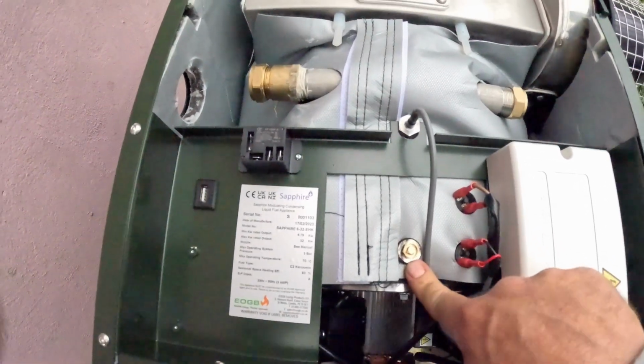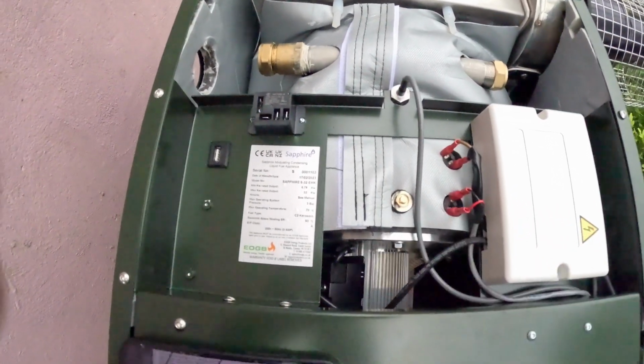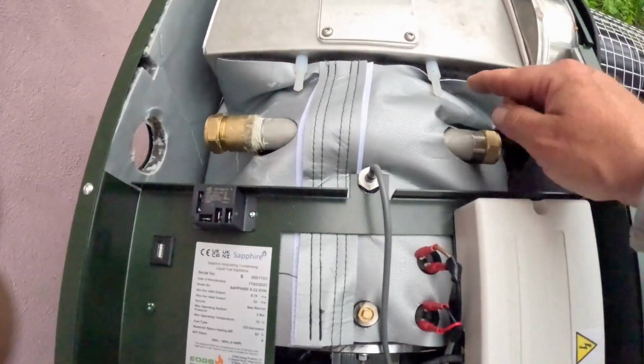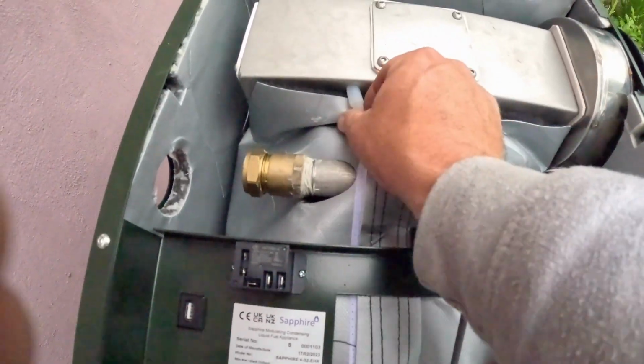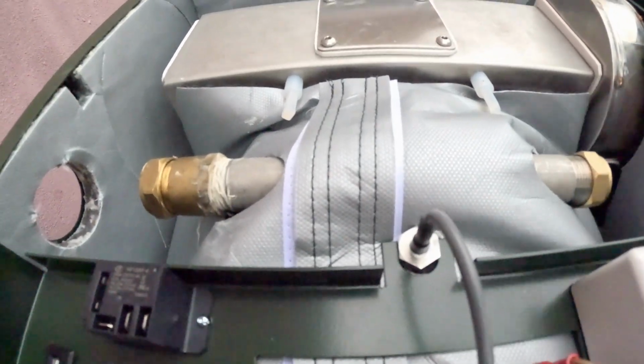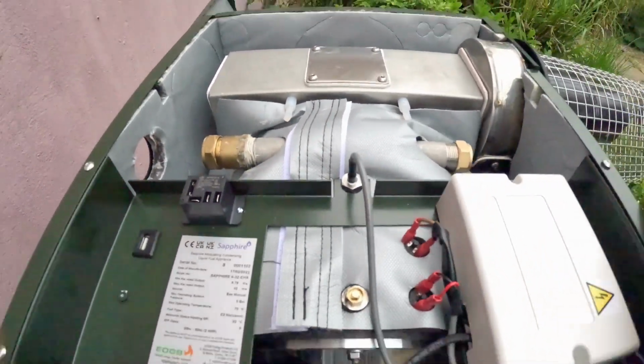Nice touch there, an air vent on the top, so you can bleed the top of the heat exchanger. Also really like this - you get two test points for the flue. Don't know why they've done that, to be honest, but there must be a reason. It's a nice option either way.